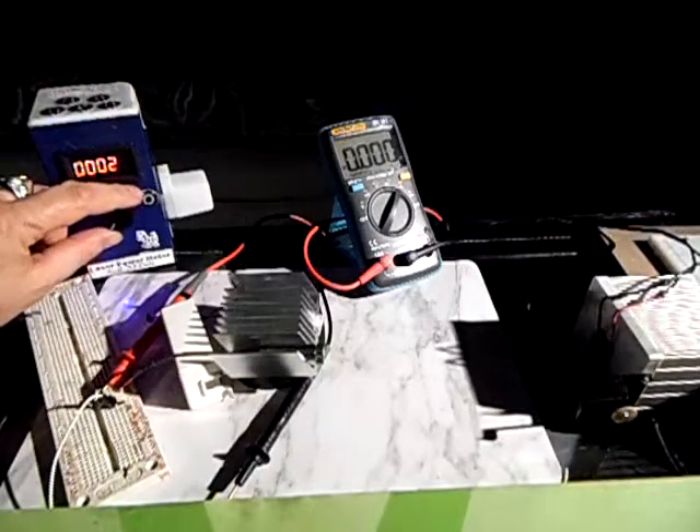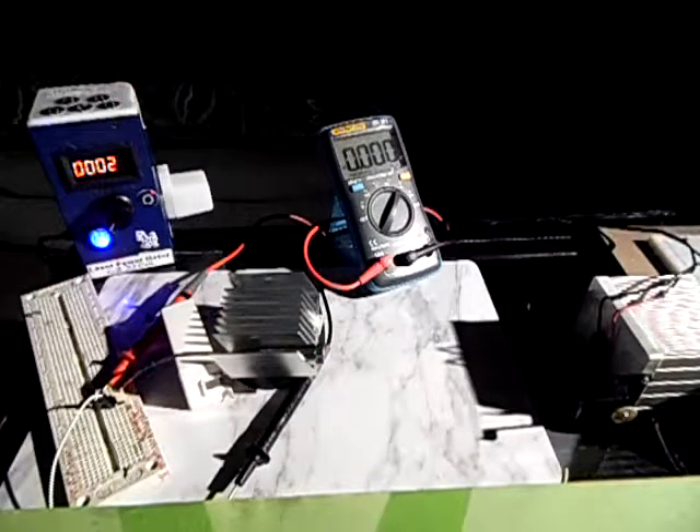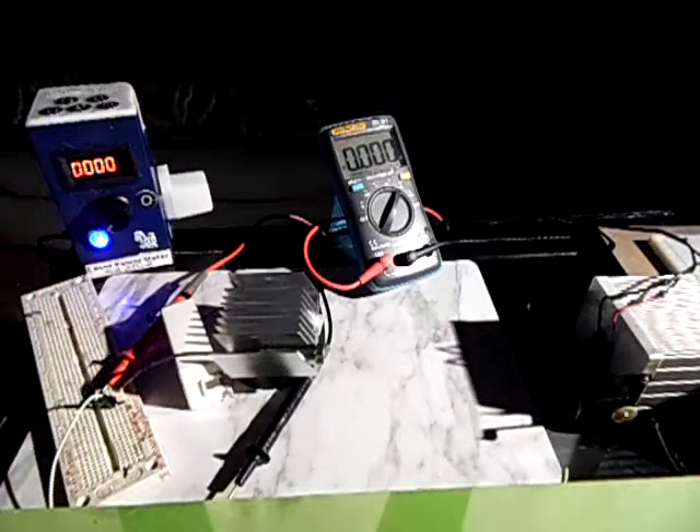You really have to get it to stabilize. When both plates are equally warm — at the same temperature — they produce no voltage, and that's exactly what you want. As long as one side is warmer or colder than the other, you will always get a voltage trying to beat the other side, and you won't get the right measurement. So you have to wait until it is stable and then you can take your measurement.